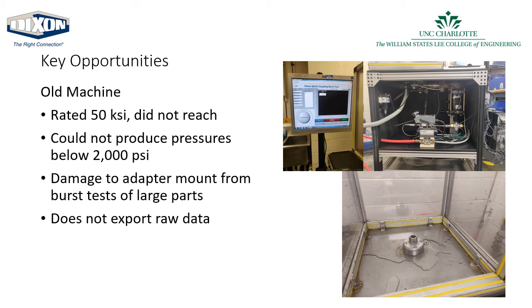So when Dixon brought us on for this project, we immediately identified some key opportunities with the old machine. Even though it was rated for the desired 50,000 psi, it didn't reach it. It couldn't produce pressures below 2,000 psi. The adapter mount would be damaged during burst tests of large parts, meaning the machine would have to be removed from service for repairs, and it didn't retain the raw data for export.